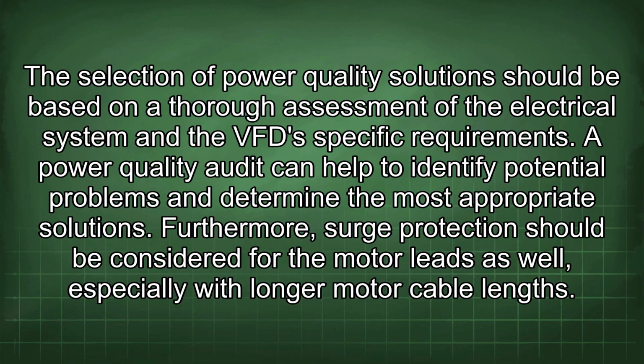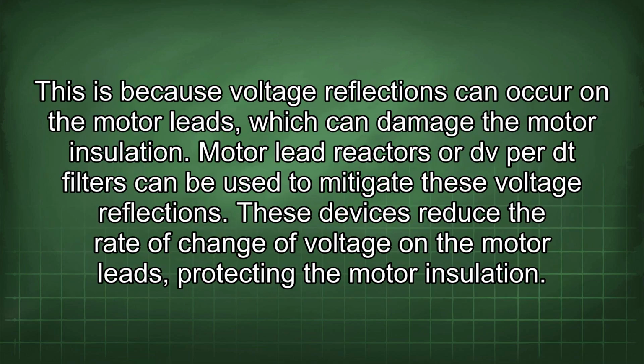Furthermore, surge protection should be considered for the motor leads as well, especially with longer motor cable lengths. This is because voltage reflections can occur on the motor leads, which can damage the motor insulation. Motor lead reactors or dV/dt filters can be used to mitigate these voltage reflections. These devices reduce the rate of change of voltage on the motor leads, protecting the motor insulation.